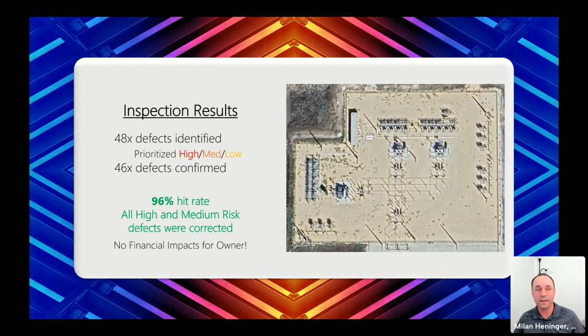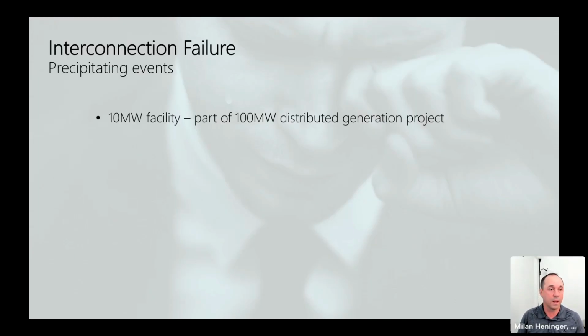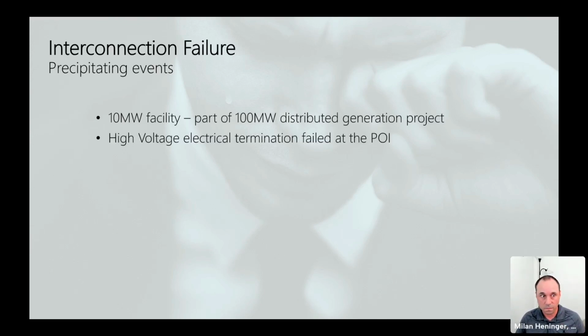Unfortunately, they're not all like this. I wish all of my stories were this proactive, but there are some that are not. And we had an interconnection failure that occurred at a facility. Now, I'm going to tell you a little bit about the background. At this particular 10 megawatt facility that was part of a 100 megawatt distributed generation project in the upper Midwest, we had a failure. And a high voltage electrical termination failed at our point of interconnection.